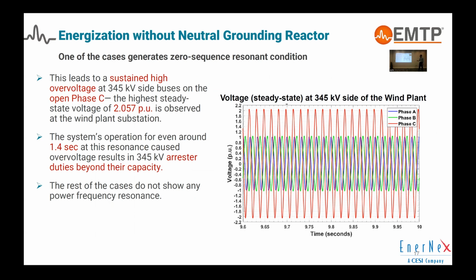So this is the steady state voltage at the 345 kV side of the wind plant. Phases A, B, C are blue, green, and red. For the blue and green phases, you see that the peak is around 1 per unit, so it's fine. However, due to the resonance condition on the pole that was stuck, we see that it is significantly higher, a little bit more than 2 per unit. And even this operation for 1.4 seconds in the EMTP simulation resulted in arrestor duty beyond its capacity. So it was very important to put a mitigation option for the project. And by the way, for the rest of the cases, we didn't see any issue.